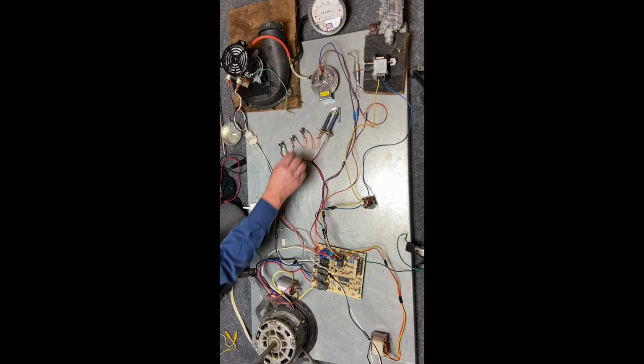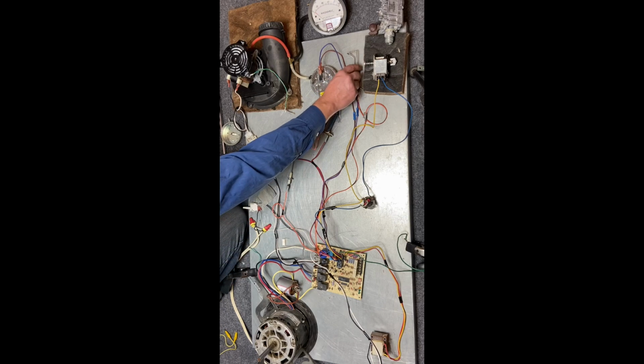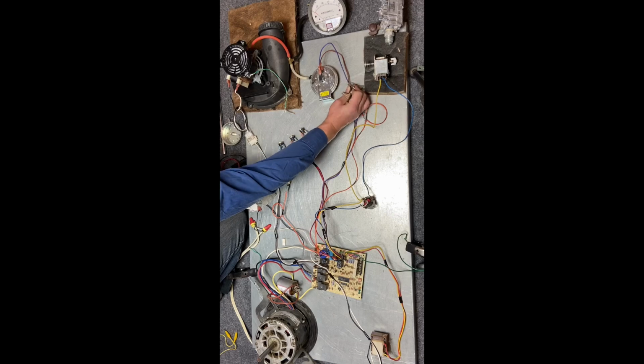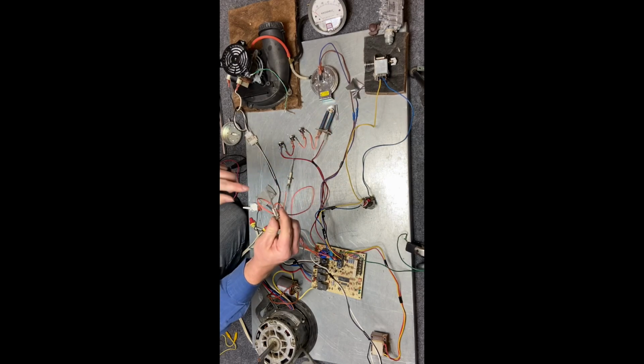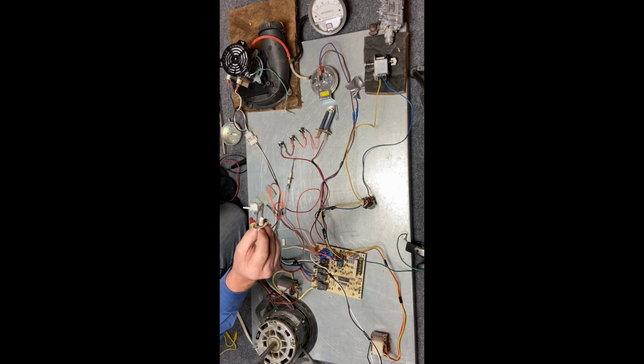And the exact same thing for our spark igniter over here. On this spark igniter, if we pull this off, we can see the discoloration between these 2 points on here. So that's one thing we want to keep in mind, is make sure we keep those cleaned.